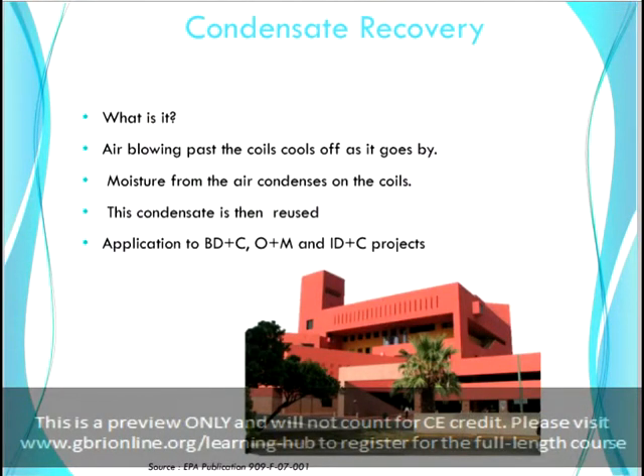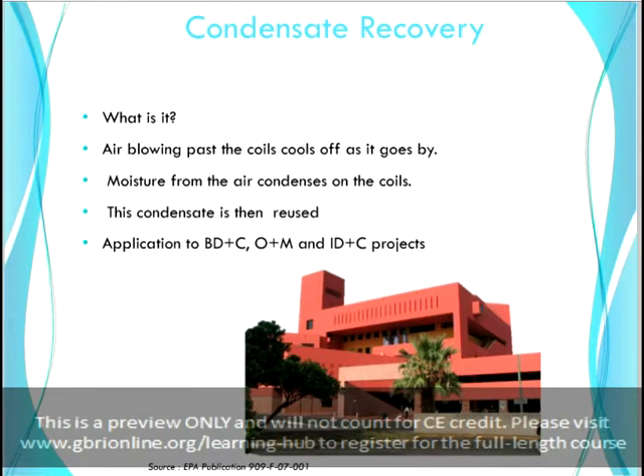Condensate recovery is an area that a lot of existing building projects are looking at. Almost every commercial building in North America is air conditioned, and more than 90% of them will have cooling. During the cooling cycle, air passes through the chilled cooling coils in the air handling units prior to entering the facilities. When the weather is hot and humid, condensation forms rapidly as air passes over the cooled coils, collecting moisture from the air onto the cooled coils. This moisture can be collected into a pan below the unit. Depending on the size of your facility and your air handling unit, you can collect a lot of water this way. You can use this condensate for various purposes such as landscape irrigation, flushing toilets, cleaning cars and equipment, and even for cooling towers.